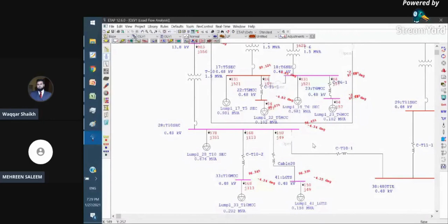So by lowering the tap on the primary side, we are actually increasing the volt per turn, and as a result, on the secondary side, we will have a better voltage profile. If previously the equipment was getting 93% voltage on the network, by reducing the tap on the primary side it may improve up to 96%, as you have seen here in the software. So you can see the profile is now improved. Wherever you have such problems, before the installation of the network, you can mitigate them by adjusting the tap of the transformer, and you can keep the voltage levels within the acceptable limits from IEEE. So I hope I am done with the presentation. I've explained the most important things to consider when we are in the simulations.